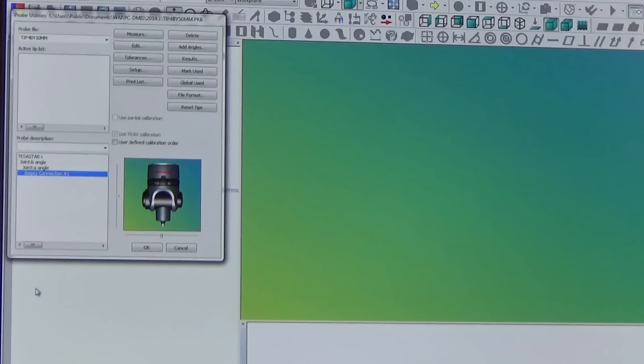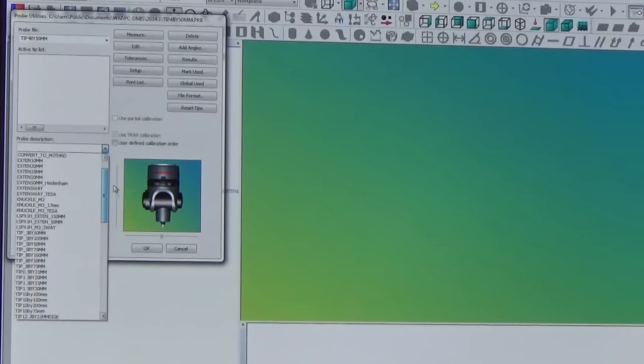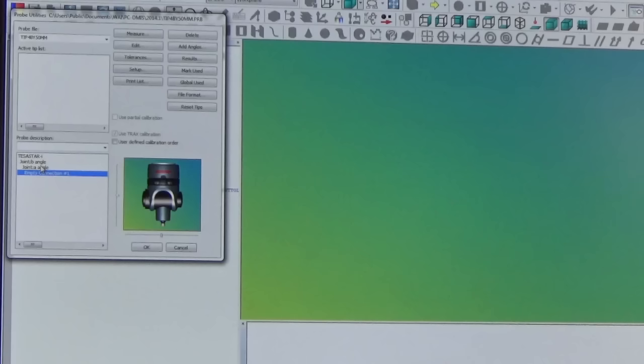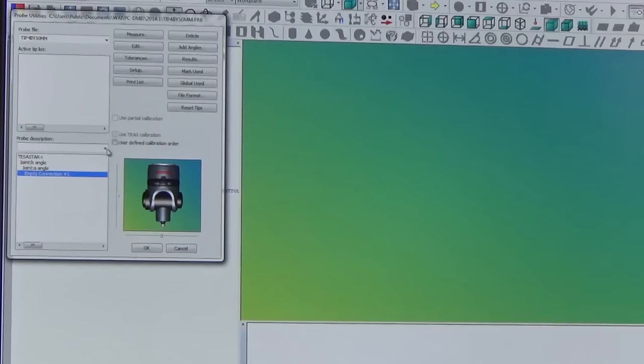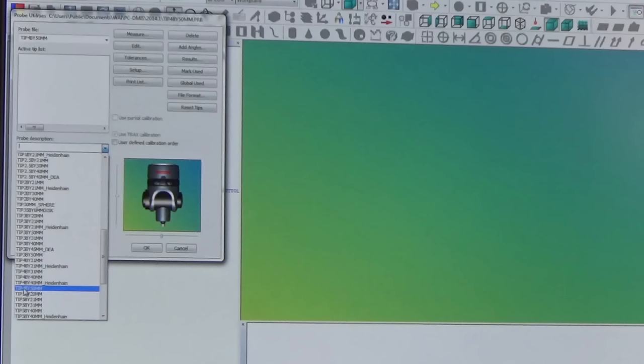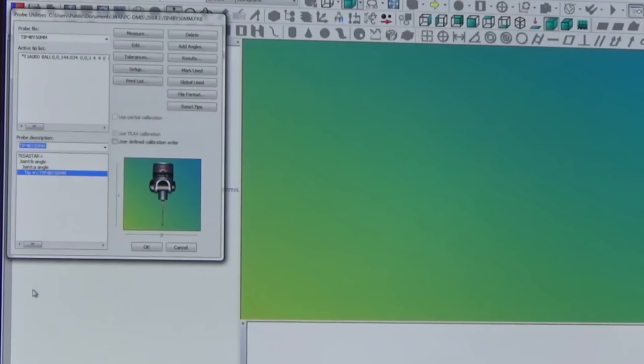So initially I have to click on this thing that says no probe defined and then in this drop down there's a variety of wrist pieces of information. In this particular case I have a TESASTAR-i wrist and it shows it in the picture there and then on top of that there are joints. And now I have to actually put our tip on to there, so our tip is 4 by 50 millimeters. So this is just the beginning, we just told it what hardware we have in place to start making our calibration.